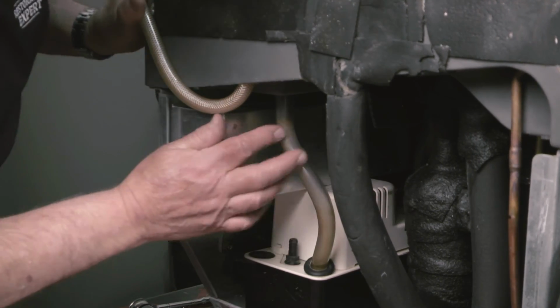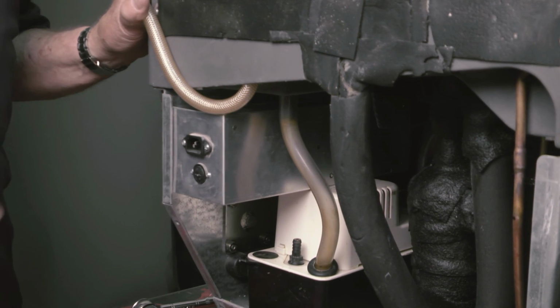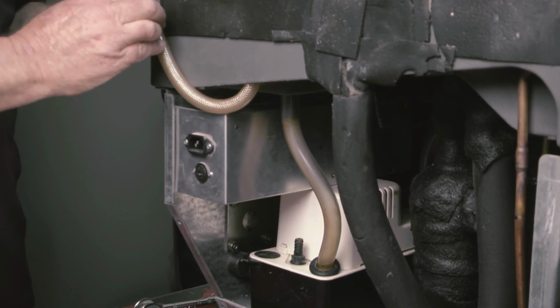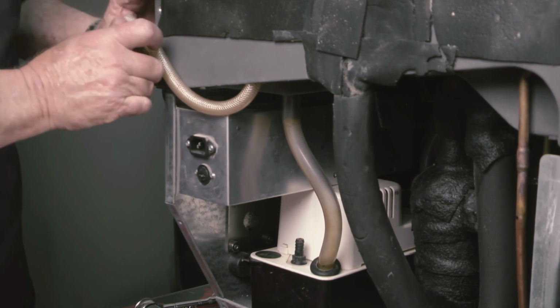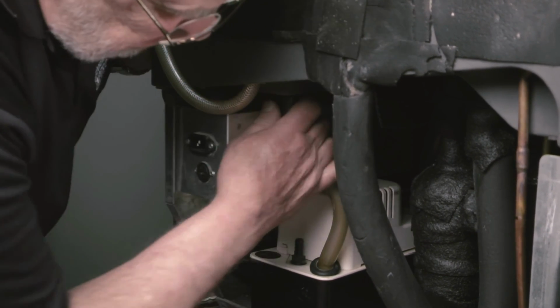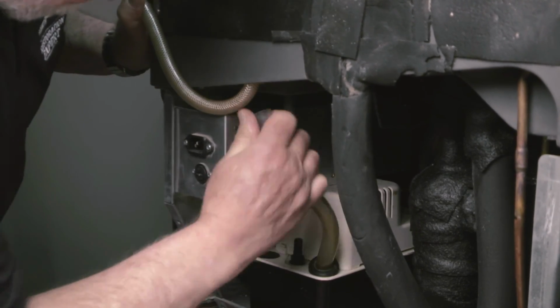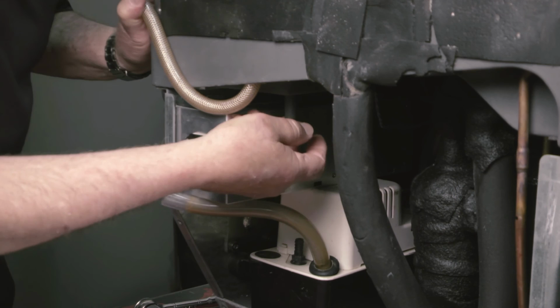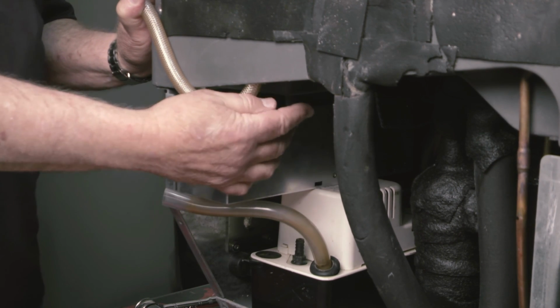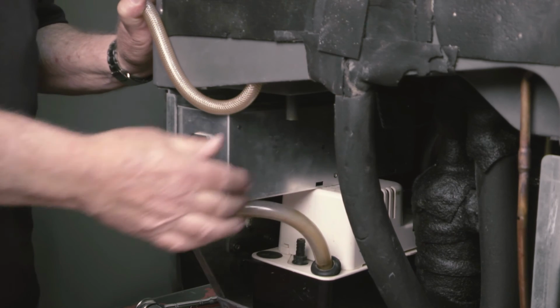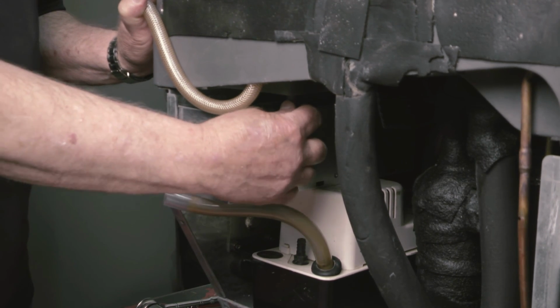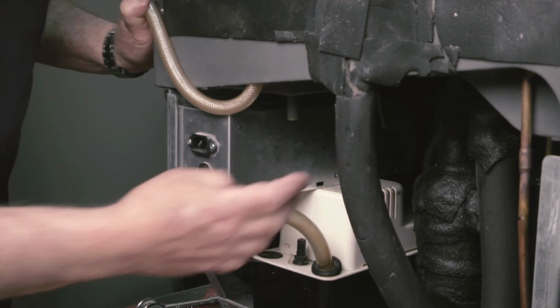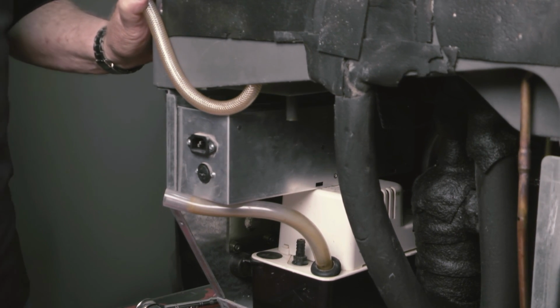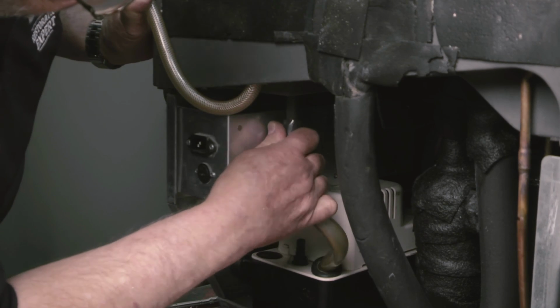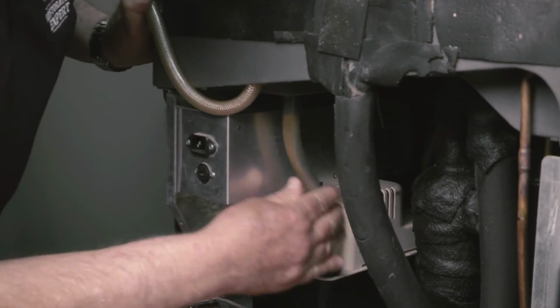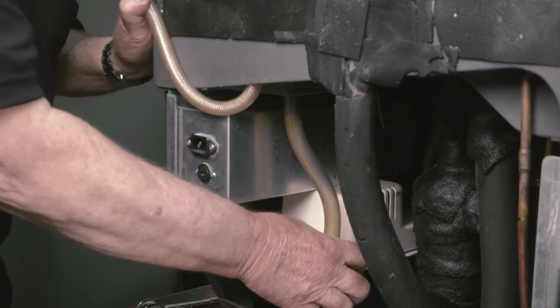One thing to note is that if you get a unit that's leaking out of the drip tray above or below the coil, what you want to do is pull this outlet hose off and clear this opening. They do get plugged up if somebody's not doing regular maintenance and a lot of debris gets in the drip tray, then that outlet will get plugged up and the unit will leak. So pay attention to that, and it will make your life a lot easier.